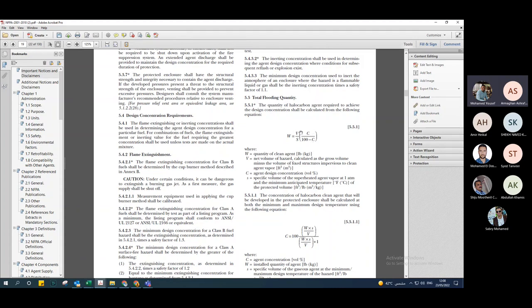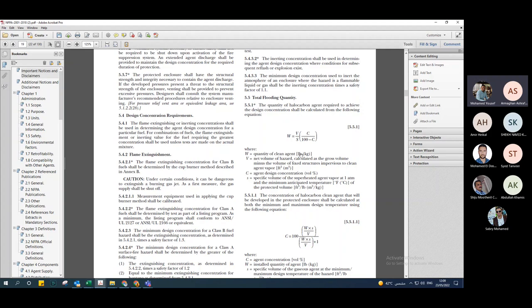The formula from NFPA 2001 is: W = (V / S) × (C / (100 − C)). W is the quantity of gas in pounds or kilograms. We will check how to calculate it in both SI units and US units.